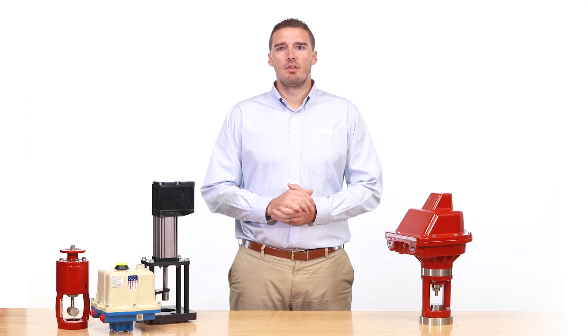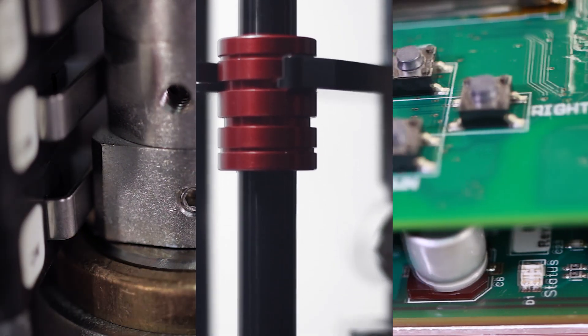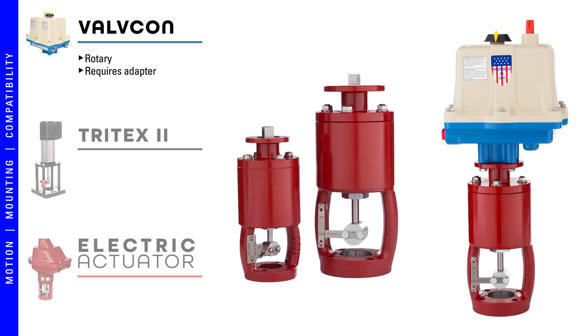Electric actuators fall into two categories based on their motion: rotary or linear. There are not many true advantages or disadvantages to either category, but rather different ways the internal components and mechanisms operate. The Valvcon is a rotary actuator and requires an adapter to convert the rotary motion to a linear motion, like on a high pressure control valve stem.